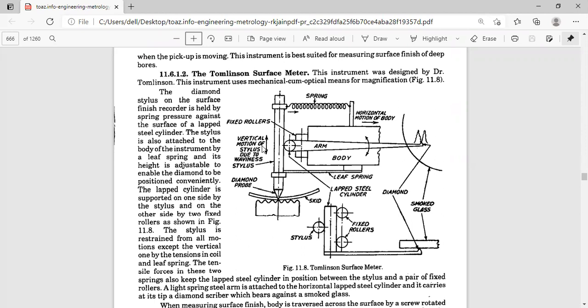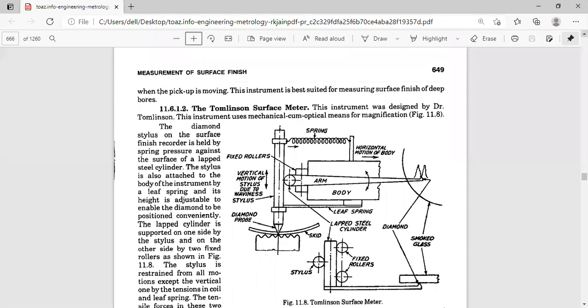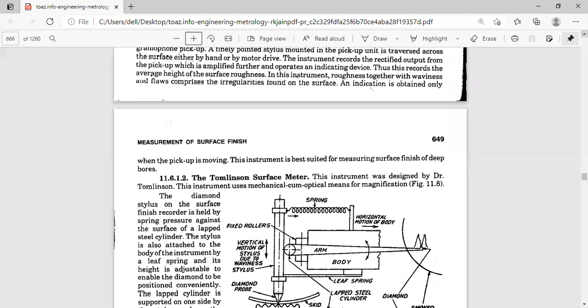This is the particular machine surface or the test surface. You want to measure the surface irregularities, and this is a diamond probe with a conical tip or a spherical tip, as we have mentioned here. What are the types of tips you can have as far as the probe or the stylus is concerned.